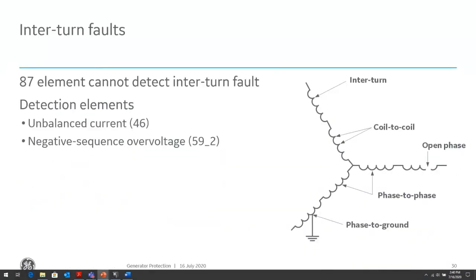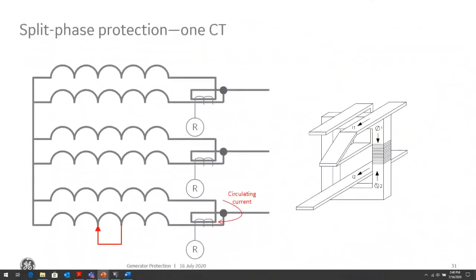Inter-turn faults or coil-to-coil faults will not be seen by the differential element, and we'll see in the next slide why that is. So we need to be able to detect those faults by various means, and one of the means is what we call the unbalanced current, or maybe a negative sequence current or negative sequence voltage element. This is an example of a coil-to-coil fault in the same winding. And this is applied when a generator is wound with two three-phase windings, each brought out separately out of the machine and connected in parallel. In this case, if the fault is within the coil-to-coil, the current will circulate within the windings and will not be seen at the terminals, either at the neutral or the terminal side.